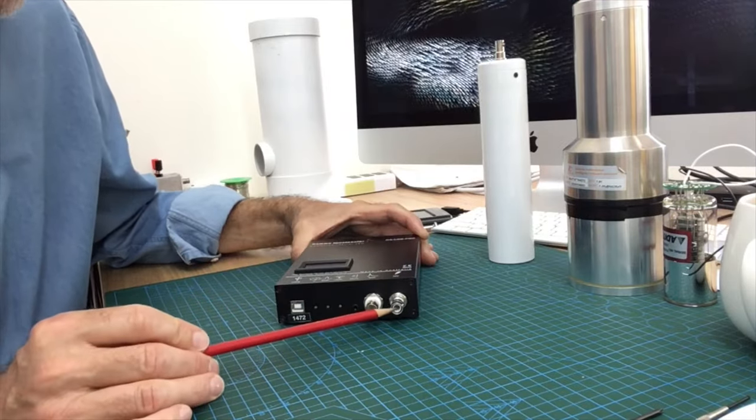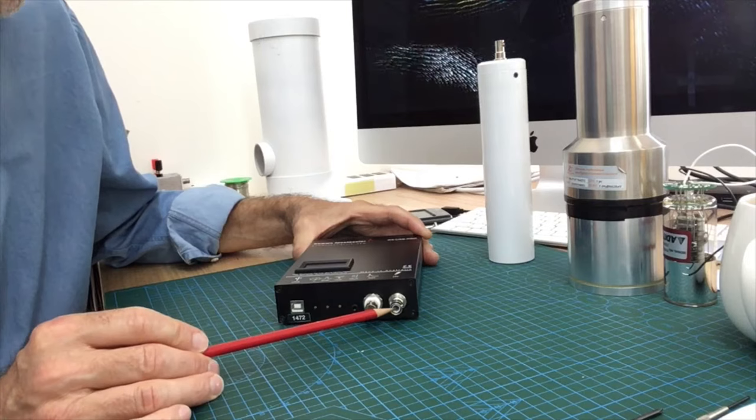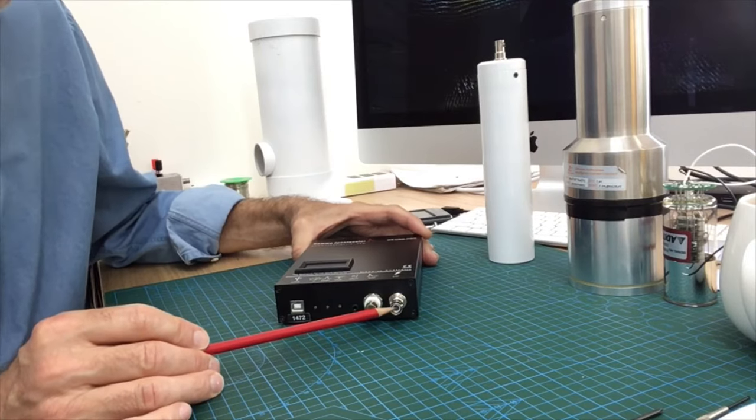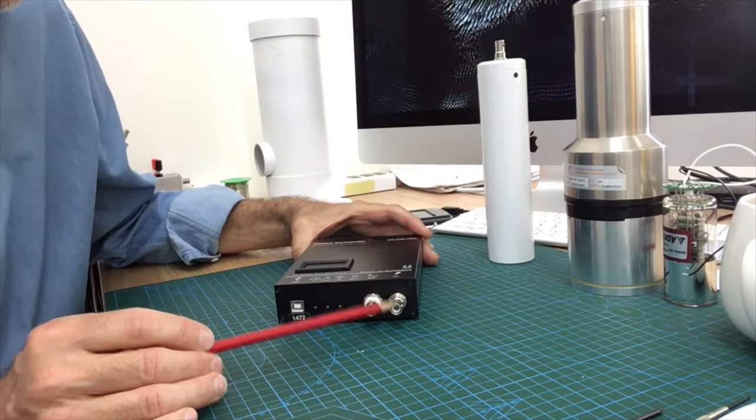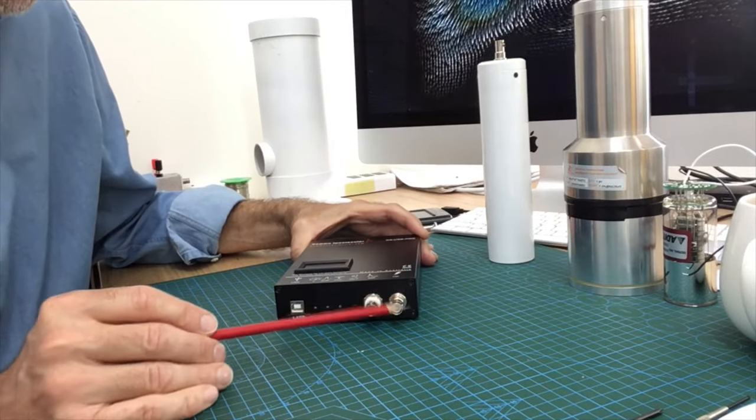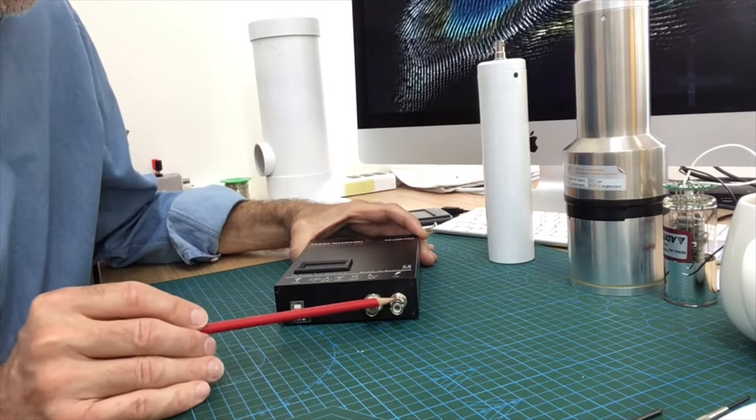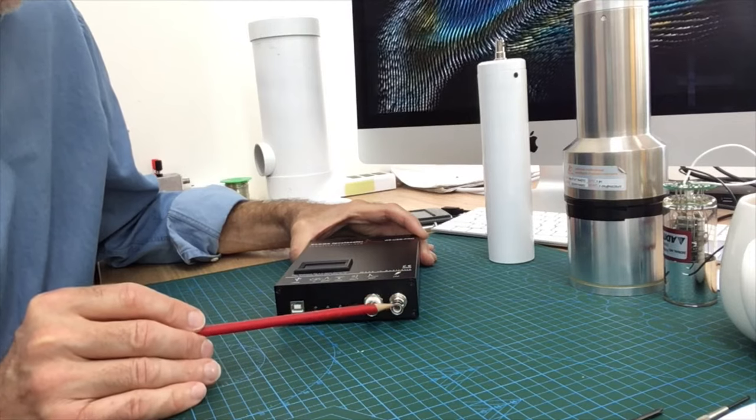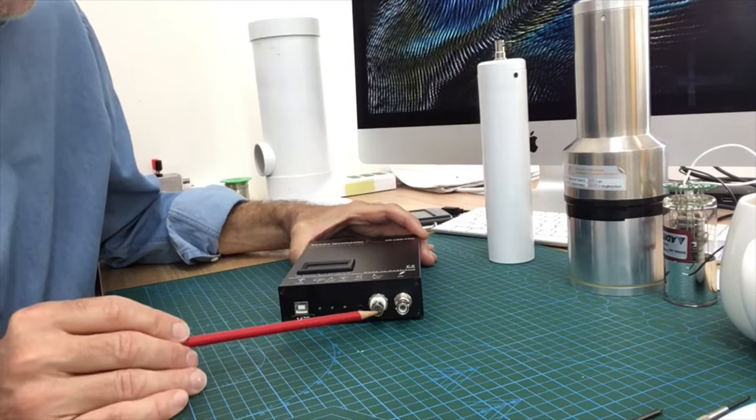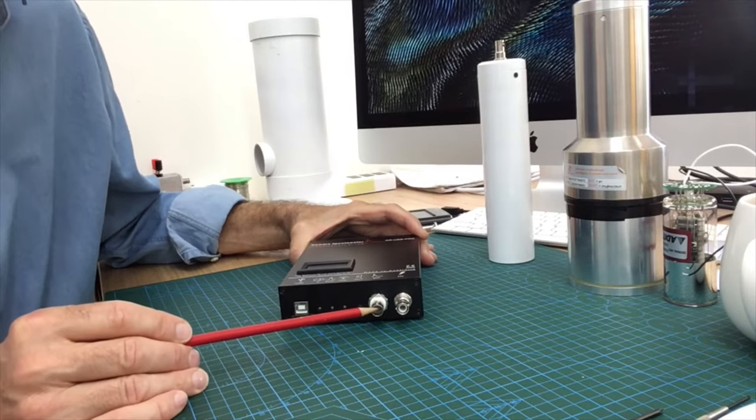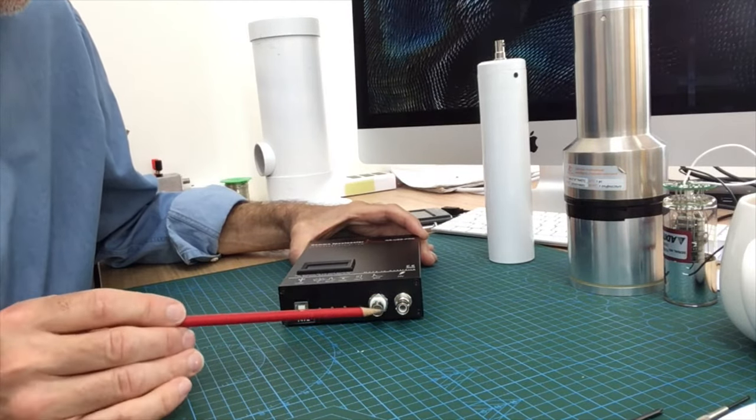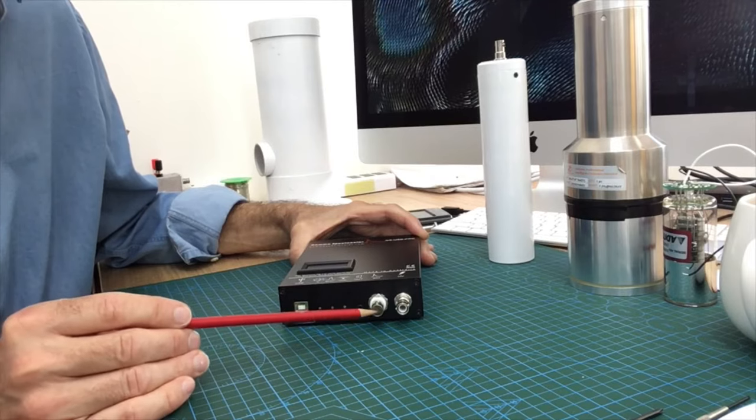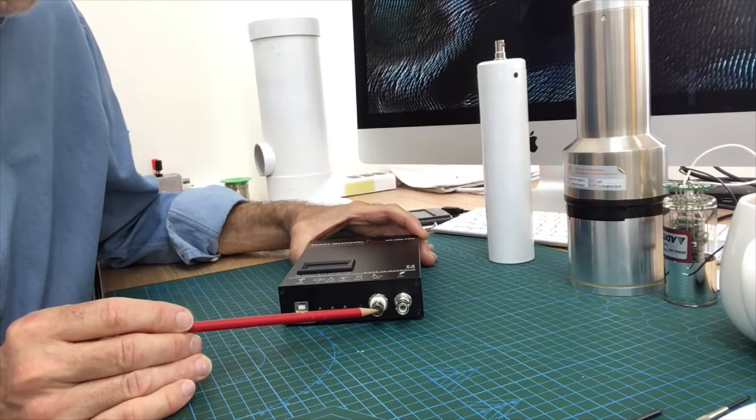Then the main port over here is an SHV connector used for the high voltage, and here is a signal input which is optional if you have a detector with two connectors.